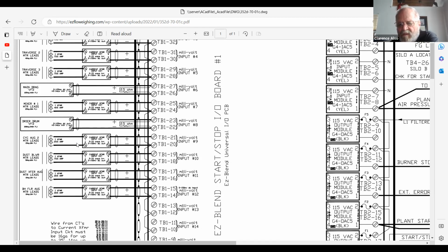So it's gonna send a button in to start up all things automatically, typically, through the IO system of the start stop control we saw before. Notice on your black modules where the little fuse is showing between like TB2-9 and the output module itself, you notice the little F5 fuse right there? Those are those little ones we were talking about the other day that look like a resistor. Okay, F5 is fuse 5, F4 is fuse 4, F3 is fuse 3. That's a good point. So those are those little things that if, as Steve just said, it's not working, you can check the module, but also check the fuse.